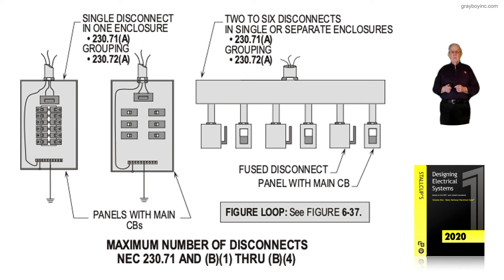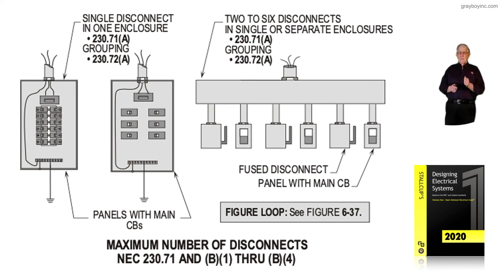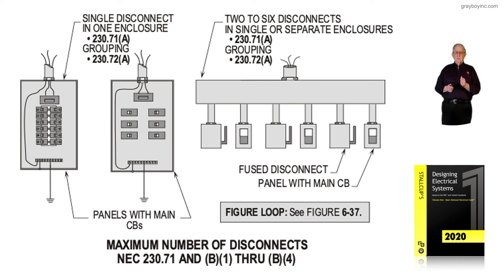When you have those two to six mains, we will also have to review — and we'll review in this chapter 6 — 230.80 and 230.90, with the exceptions, and just exactly how those mains would have to be designed. The full ampacity of those mains would not have to match the ampacity of the conductors at all when we start reviewing 230.80 and 230.90, exceptions 1, 2, or 3.